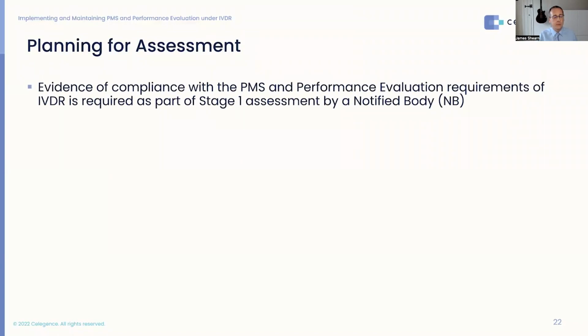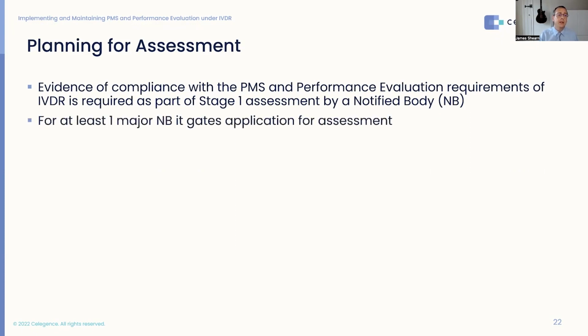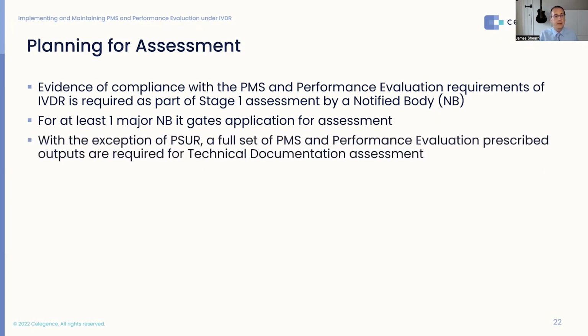When planning for assessment, evidence of compliance with the PMS and performance evaluation requirements of IVDR is required as part of the stage 1 assessment by a notified body. In fact, for at least one major notified body, it gates you actually being able to submit an application for assessment. With the exception of the PSUR, a full set of PMS and performance evaluation outputs are required for the technical documentation assessment. Instead of PSUR, you can provide a summary of the PMS history for the product, but everything else needs to be in place.